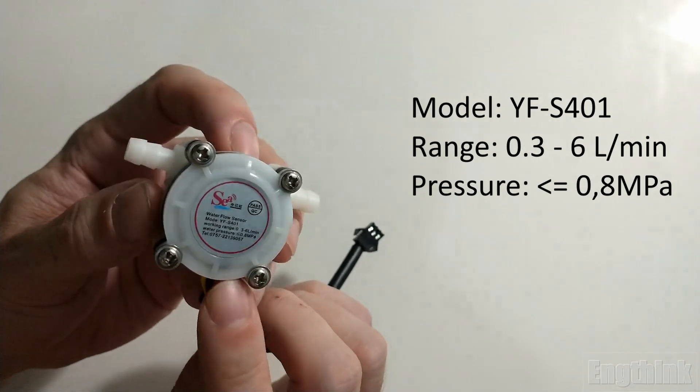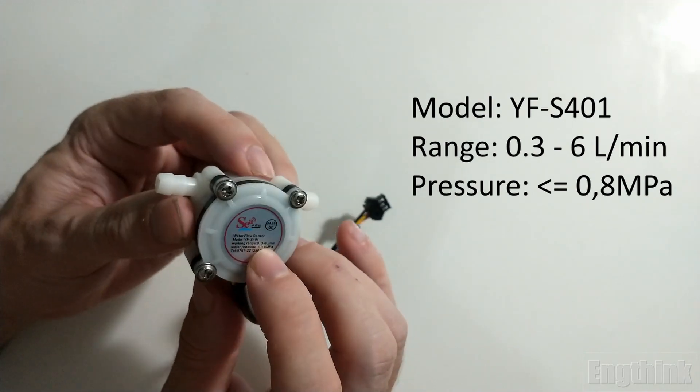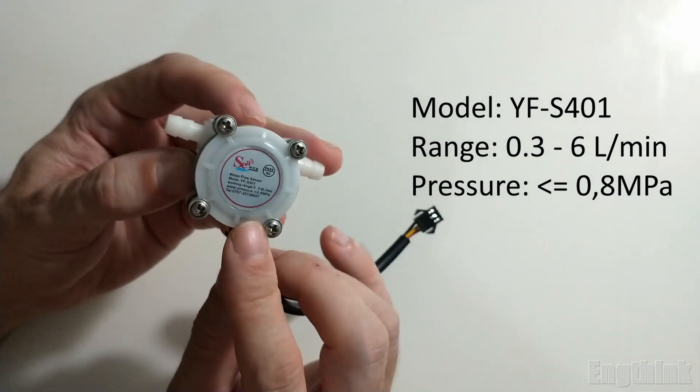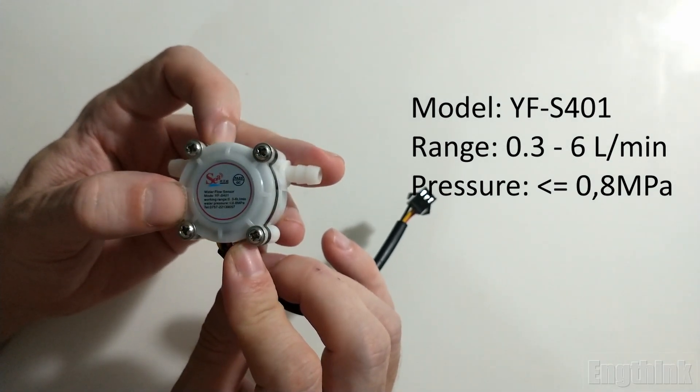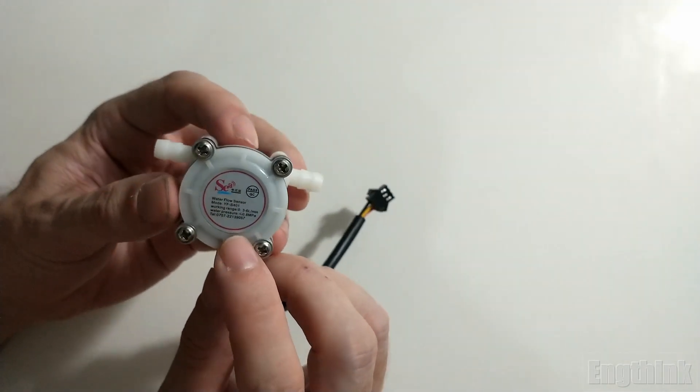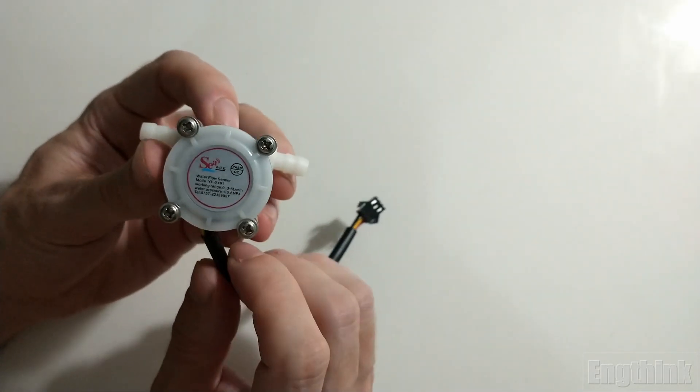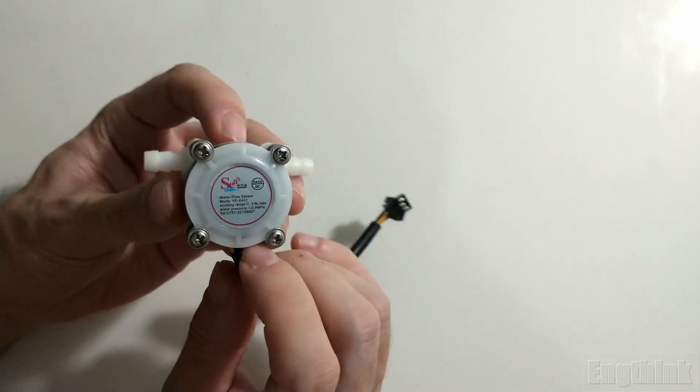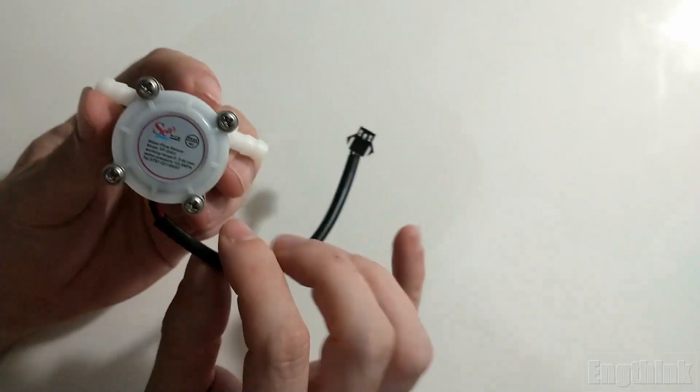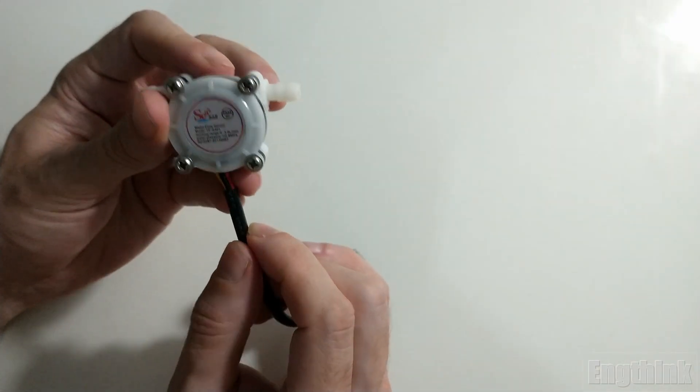However, due to its small size, there are some limitations. One of them is about the working pressure. This model can support a maximum pressure of 0.8 MPa. If you have more than this pressure, you'll probably get some error in the measurement. In the same way, if you put too low pressure, you could get some error in achieving the minimum flow value of 0.3 liters per minute.